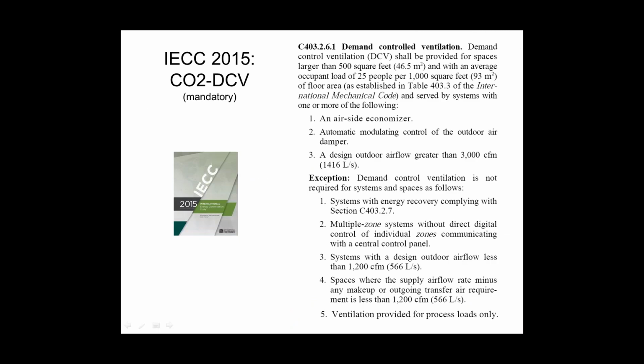The demand control ventilation rules, which have not changed at all since the 2012, are exactly the same. I just bring them up because it is a very common controls-related topic in the code. If you have an occupancy density in this particular space that has more than 25 people per 1,000 square feet, you are very likely going to have to put a CO2 demand control ventilation system on there. That sounds scarier than it is. It's not hard to do that.